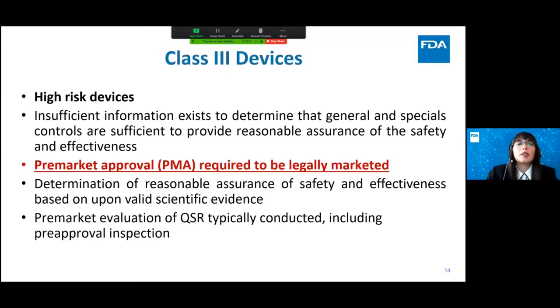Class 3 devices: this is where insufficient information exists to determine that general controls or special controls are sufficient to provide reasonable assurance of safety and effectiveness. These devices do require pre-market approval, or a PMA, in order to be legally marketed. And the determination of reasonable assurance of safety and effectiveness is based on valid scientific evidence. Again, that could be done through testing or clinical information through literature, registries, a clinical study. Those are typically some of the scientific evidence that we do review when we're looking at these devices.